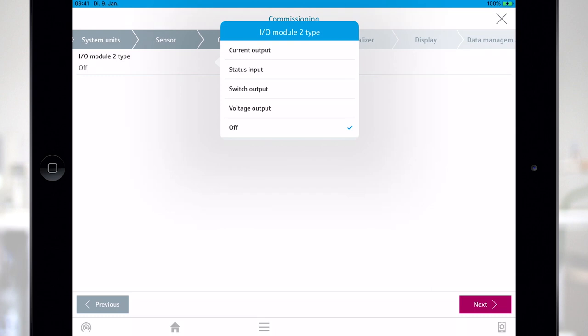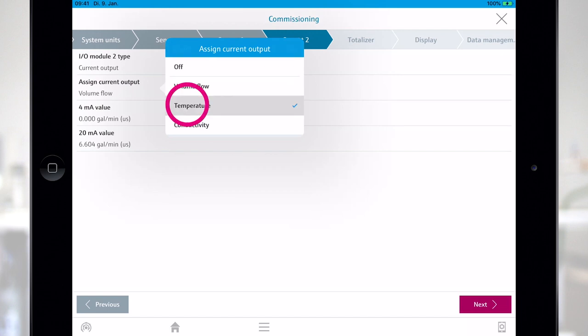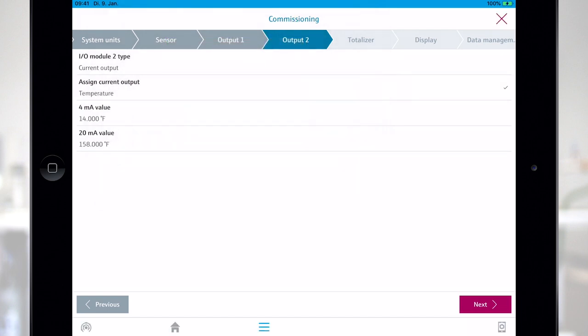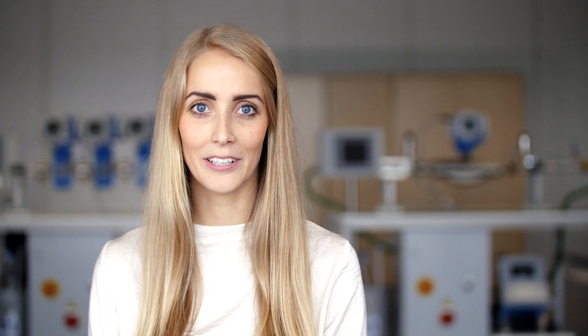For the second output I've chosen current output. Now I can assign the output to temperature for example and then easily configure the 4 to 20 milliamp values. Now configuration of output 1 and 2 has been successfully completed.